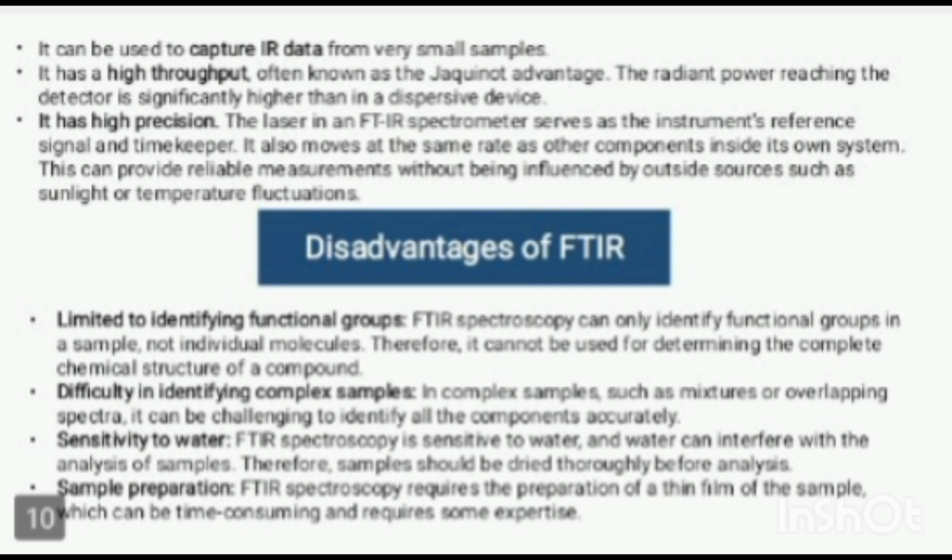Next disadvantage is difficulty in identifying complex samples. In complex samples such as mixtures or overlapping spectra, it can be challenging to identify all the components accurately. Sensitivity to water. FTIR spectroscopy is sensitive to water, and water can interfere with the analysis of samples. Therefore, samples should be dried thoroughly before analysis. Last disadvantage of FTIR is sample preparation.